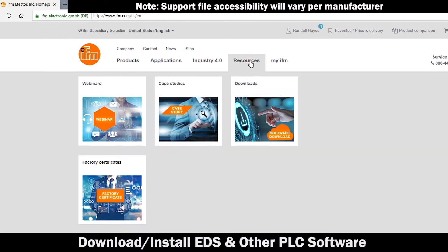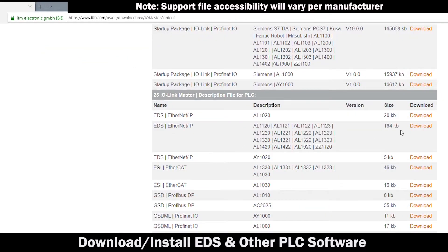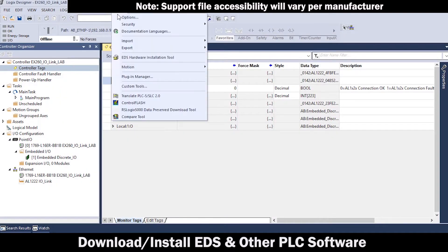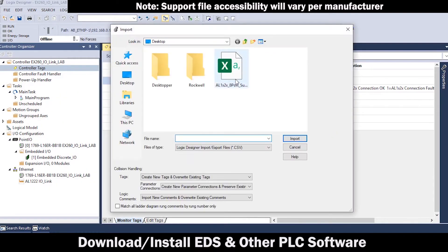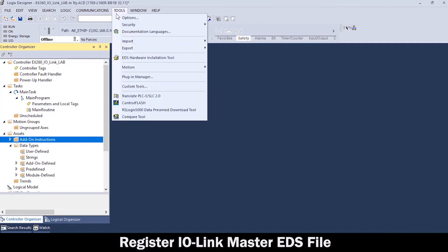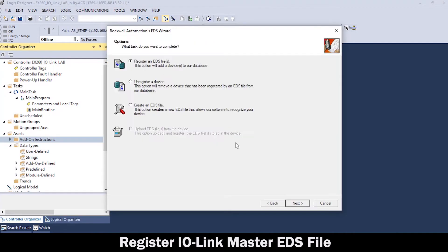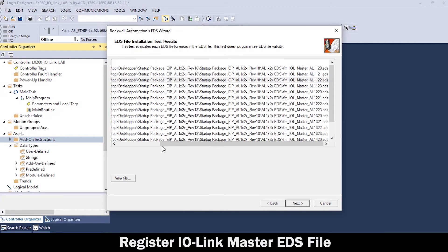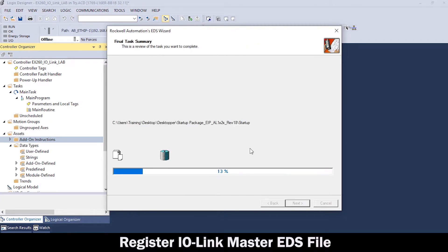Download the EDS file from the IO-Link Master manufacturer. Also, download all necessary files for PLC access support, referring to manufacturer specifications. Now, with the IO-Link network running, start a session of Studio 5000. Then, select and add the IO-Link Master EDS file and click Finish.